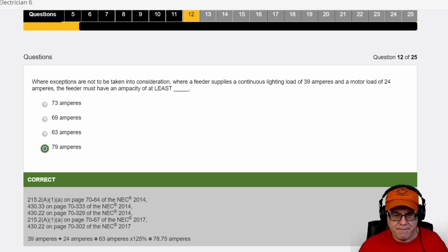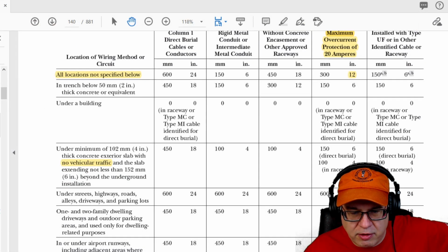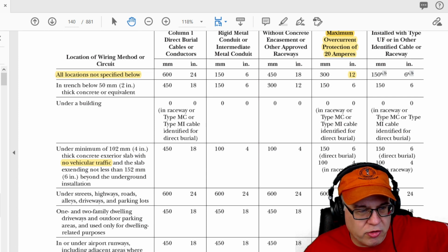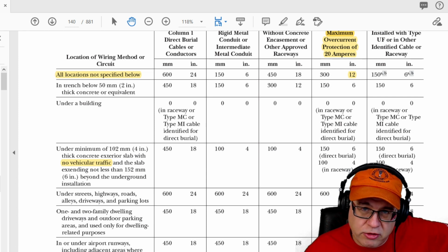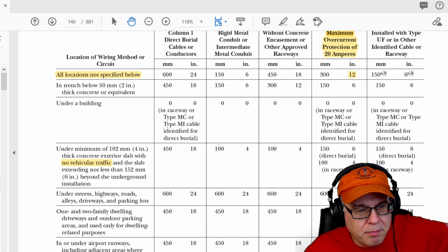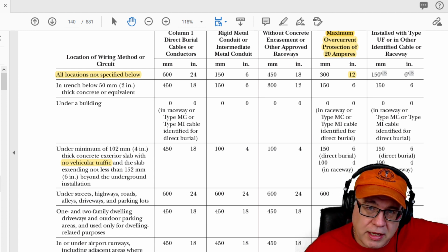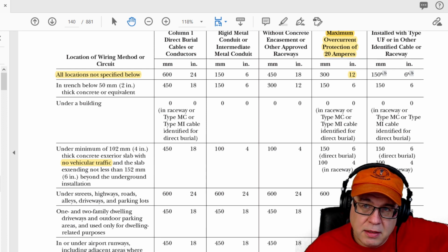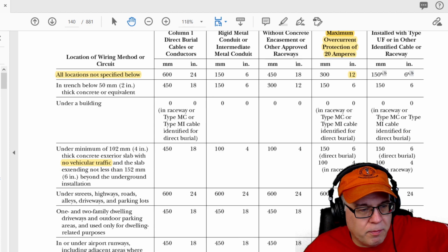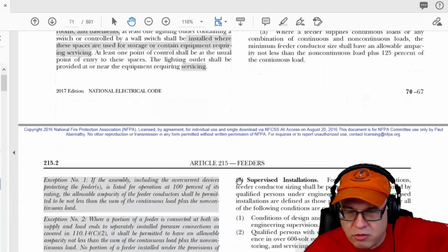All right, and the code references again on this one, as you can see them all here. But it wasn't exactly what you think, because each one of these, again, because it was a feeder, is the key for this one for me. I want to show you that so you understand, because you know motors, you get it, because that's where you got the 430.22 that's going to say 125. But then you also know the other load is considered a continuous load. So what did we do? One way I would approach feeders, and I'm going to show you.